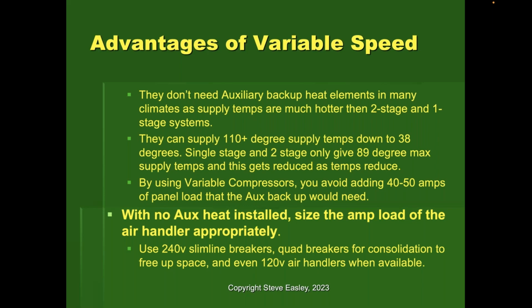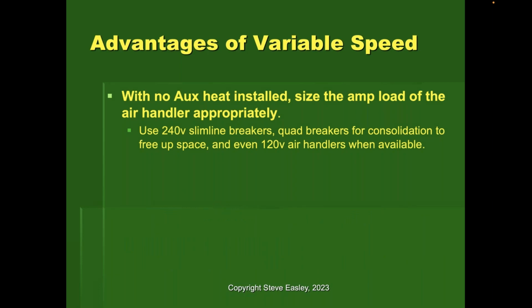So if your air conditioner is cranking away, which it usually would be at 3 o'clock in the afternoon, and you're on solar and you have battery backup, boy, these batteries can't handle the big amp draw of these larger compressors. So having the variable speed inverter-driven compressors are much more battery friendly for those of you that are trying to offset those peak loads and flywheel through those peak times of the day. But with no auxiliary heat installed, we size the amp load and air handler. You want to make sure you size those appropriately, and pay a little closer attention to that.